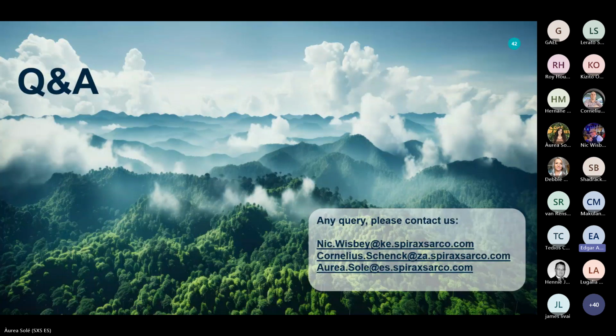My question is in regards to the last point that you highlighted on decarbonizing of the boiler. To the best of my knowledge, I'd always based on the flue stack temperatures to determine whether the boiler needs decarbonizing or not. Basically, if temperatures go above 180, 180 to 200, above that, I would then sanction for decarbonizing. But I see in certain operations, they just put it up as a routine, and I don't know if that is actually helping. For example, if you do the decarbonizing twice a month, does that add value for a boiler that's running on heavy furnace oil and runs about 8 to 10 hours a day, maybe 5 days a week? I just needed some clarity on that.